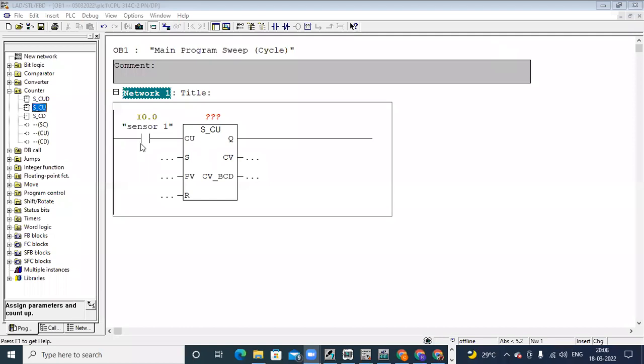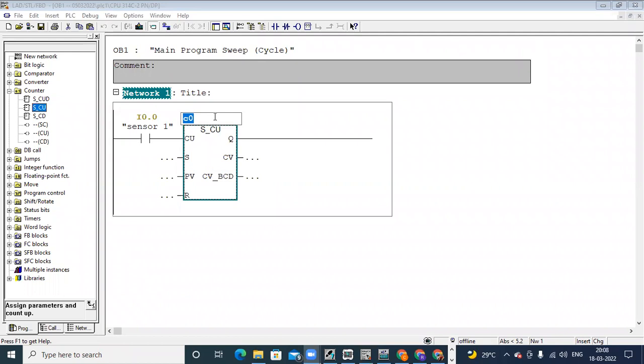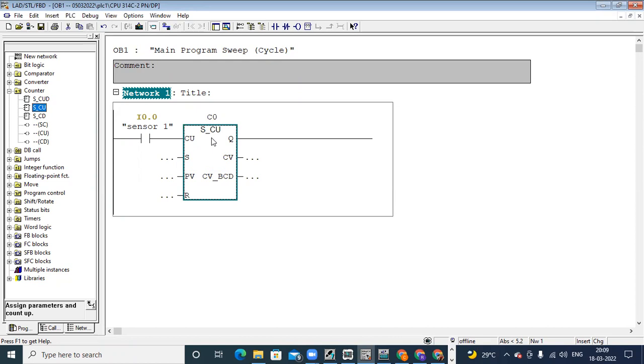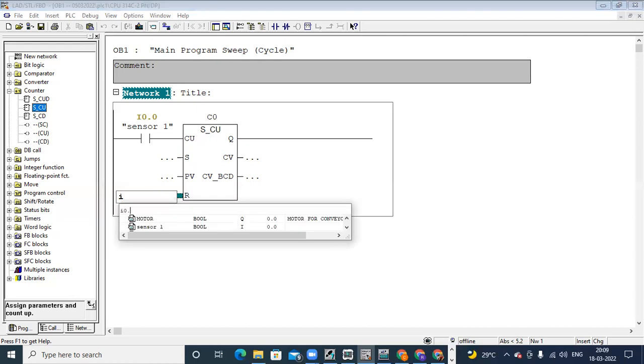I just rename them. Put the input address as Sensor 1, then counter number C0 — it also auto-numbers starting from C0, C1, C2, C3 like that. The range of counters depends on the PLC. Some PLCs support 64 counters, some 120, some 2000 — it depends on the PLC type. Next, S is a set input — it is also a boolean input. When I move the cursor to PV, that is called preset value; it's a word address.